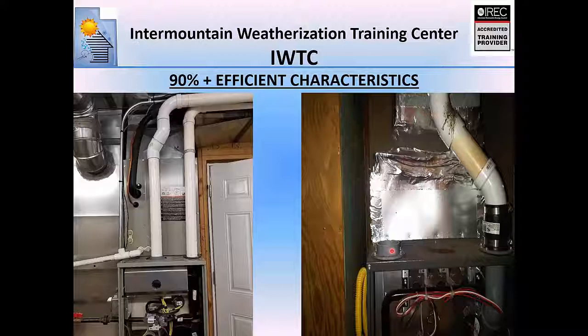Now the manufacturer of this particular equipment will allow you to install it this way. It's no longer a direct vent appliance. It falls under a different set of rules for terminating the flues. Okay, this is absolutely not allowed in our program. We should always run two pipes, and if you can get one out, you should be able to get the other one out. But the problem with this now is it's become very unsafe because now this could backdraft and the products of combustion will spill right out of this guy into the house.